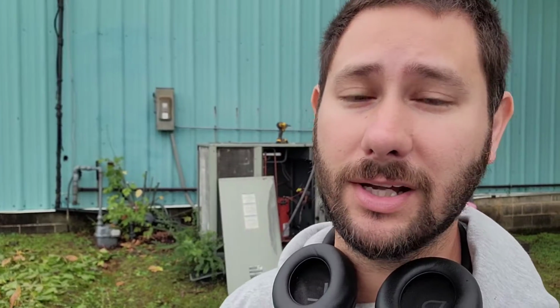This right here is 410A. I didn't see a reason why I shouldn't do what I did, and I'm going to give you this information so you can do this in the field too, because you can gain a customer for life. The other heat and air companies said compressor or new outdoor unit. I said, we have a third option. Let's get the other section of the unit running, because they're separate. You've got two 7.5-ton compressors. Why not get one section of this condenser running so you still have some air, and you don't have to worry about buying a new unit until next year? They have gas furnaces inside too, which I'll show you in just a minute.